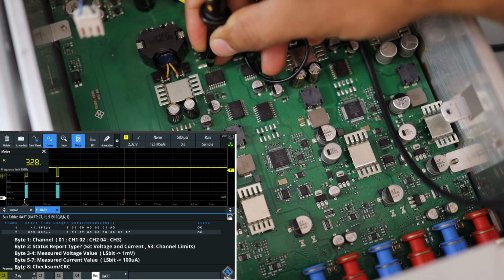Yeah, okay. So right now my channel display is green, so value is 1, and now I will connect. My channel is red, meaning it's current limiting, so value is 3. So this is representative of the channel status, if it is overloaded or short circuit or current limited or voltage limited. One means at least voltage compliance, and the second means that we have reached the current limit maximum. And this is current, channel state, voltage. So the same thing will happen for other channels as well. Instead of one, you will have 2 or 4, and you will see what the value is.